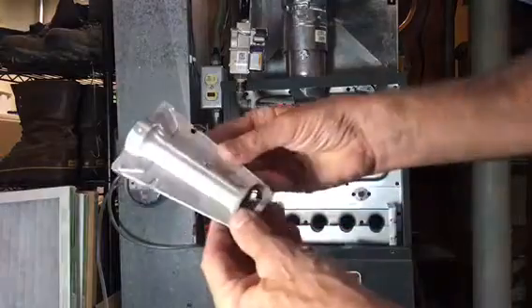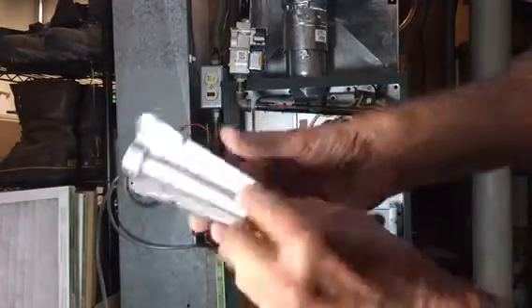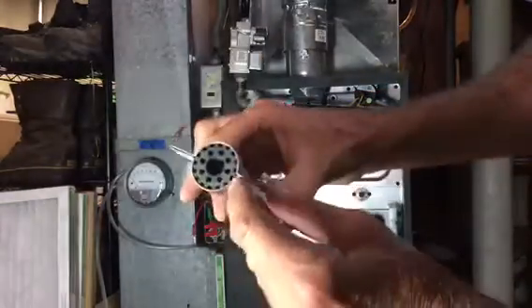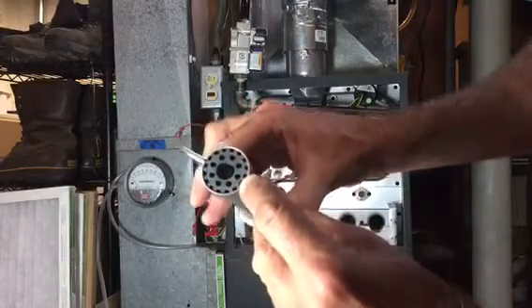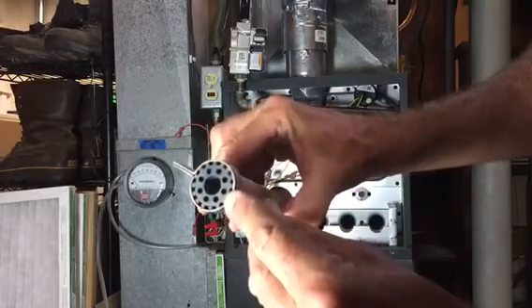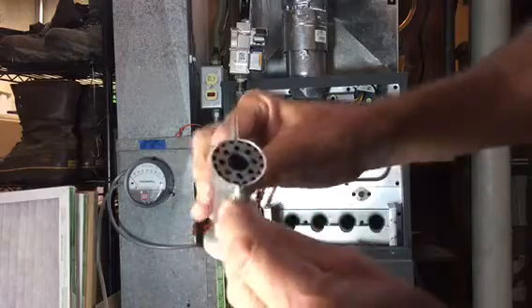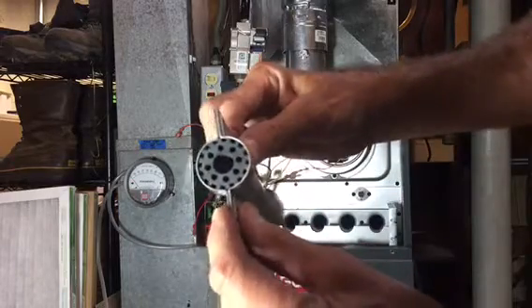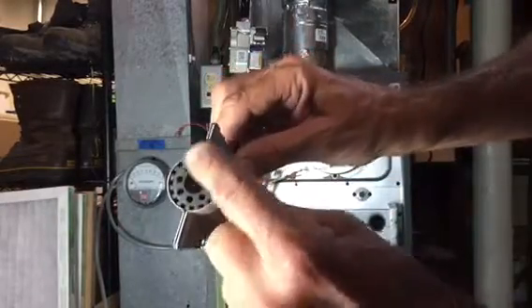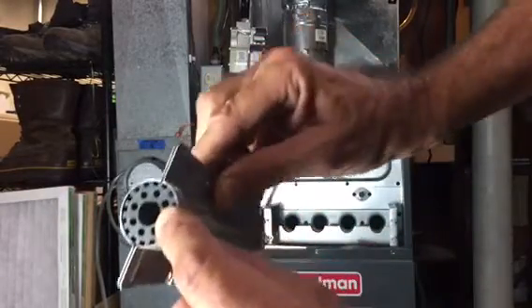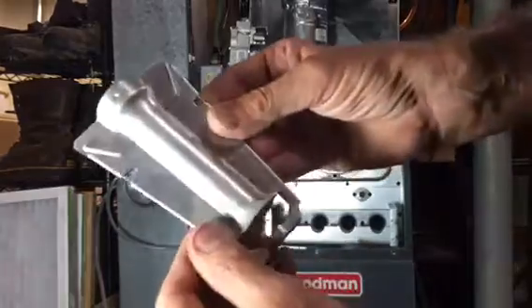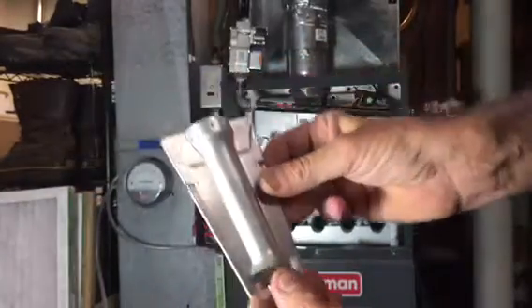Okay, here's the burners removed. They're just stamped metal with a cast jet fitting at the end that forms the flame. Just to make sure this is clean, it looks pretty good. I'll probably blow it out with air. There's a little dust in there, but there's no corrosion. All these holes are looking pretty clean. This is representative. They're all about this size.